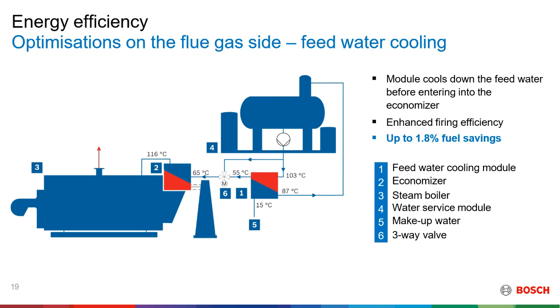Reasons for cooling down the water is you're trying to increase the temperature gradient against which heat transfer happens. So here, instead of taking water at 103 into the economizer, you're taking water at 65 degrees, which is able to pick up more heat compared to water that is flowing at 103 into the economizer. This way, you're able to pick up more heat or maximize your economizer. Okay. Just a point to note again. Here we assume the feed water tank is under full deaeration, and it's a completely pressurized tank. So therefore, as you cool down the water, you will not have reintroduction of air into the water.